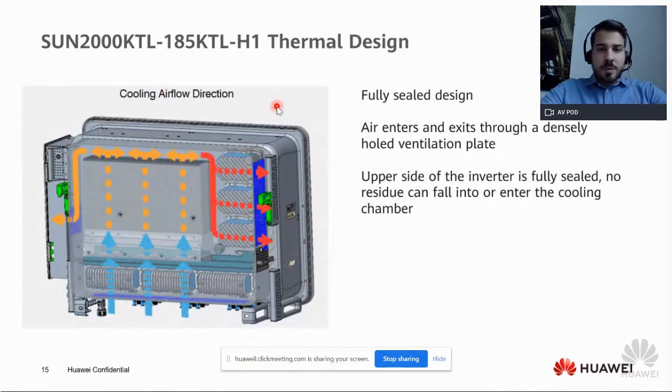Regarding the thermal design of the inverter, it is a fully sealed design. As you can see, the air enters here via the densely holed ventilation plate. It will go through numerous air ducts, and it will be driven to cool down the whole device. We have 3 fans included in the system. This will give us a higher flow of air to circulate.